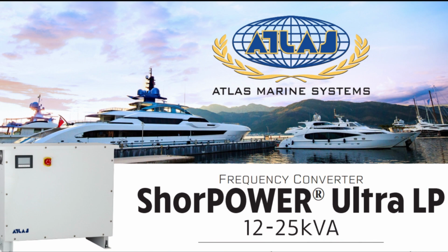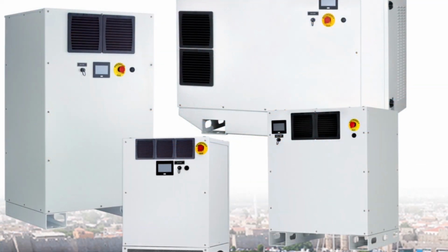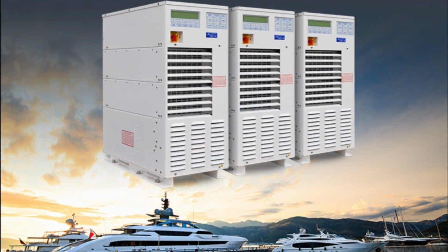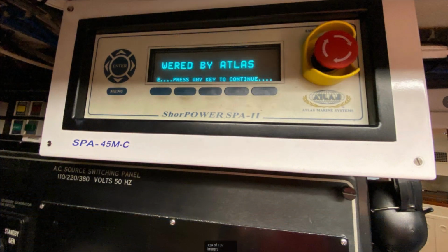If you are intending to travel outside of North America for an extended period of time, you might want to consider going with a frequency converter, which will do everything that an isolation transformer will do, plus convert 50 cycle power to 60 cycles, or vice versa. They will also accept a far wider range of voltage, typically from around 170 volts to 520 volts.